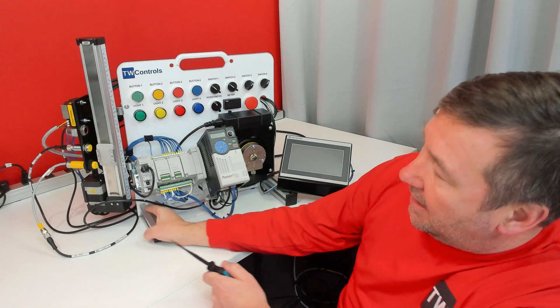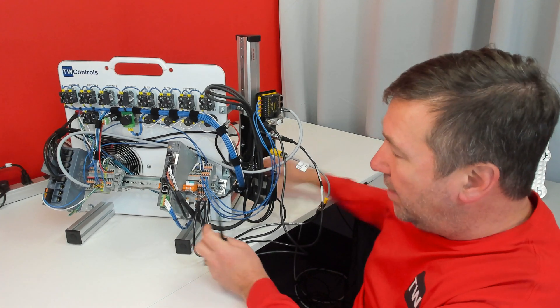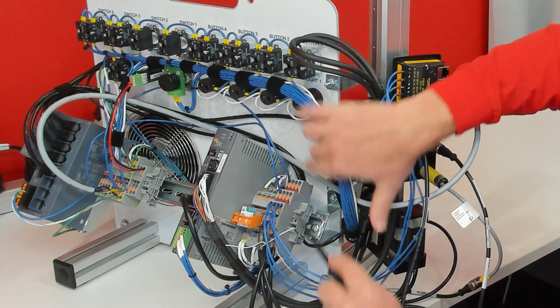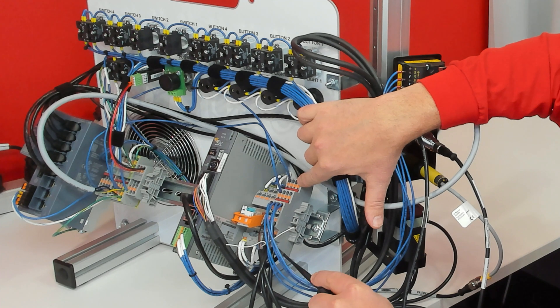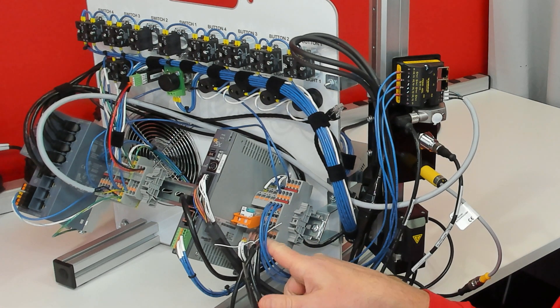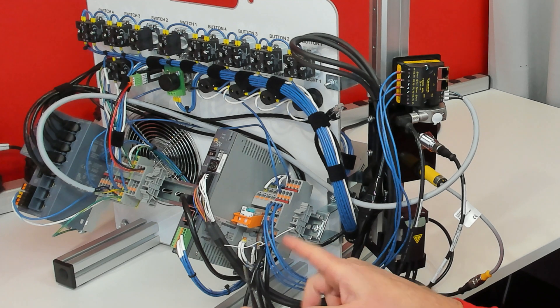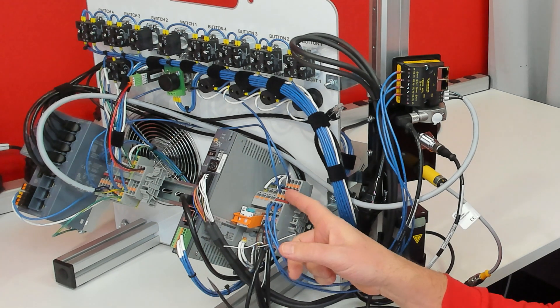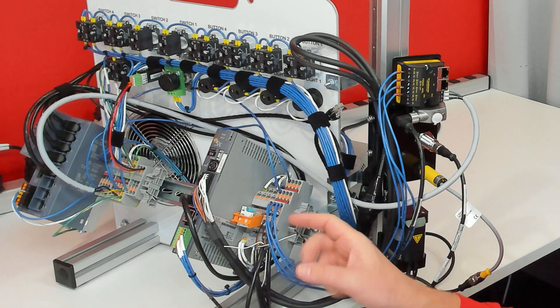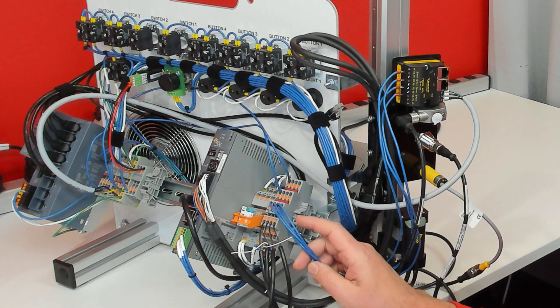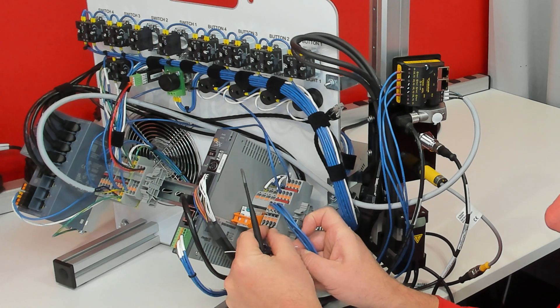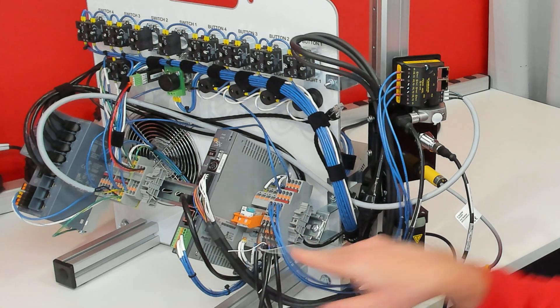So now what we want to do is, in our previous exercise, we wired two of these sensor inputs here, and the back level, that is our minus 24 volt. And we already have all of our blue wires there, so they are already wired. Even though we did it for the IO-Link, the wiring will be identical. And then our middle level, we put plus 24 volt, and we already have all of our brown wires going there. And so then our top level, that's where we landed all of our black terminals. And right now, those are going up here to this IO-Link.